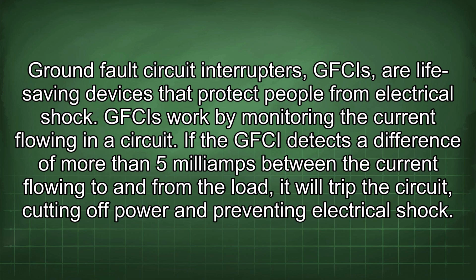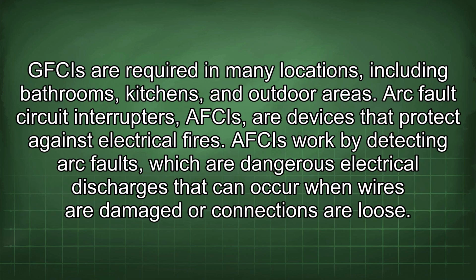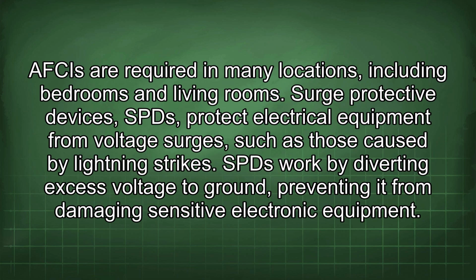Ground fault circuit interrupters, GFCIs, are life-saving devices that protect people from electrical shock. GFCIs work by monitoring the current flowing in a circuit. If the GFCI detects a difference of more than 5 mA between the current flowing to and from the load, it will trip the circuit, cutting off power and preventing electrical shock. GFCIs are required in many locations, including bathrooms, kitchens, and outdoor areas. Arc fault circuit interrupters, AFCIs, are devices that protect against electrical fires. AFCIs work by detecting arc faults, which are dangerous electrical discharges that can occur when wires are damaged or connections are loose. AFCIs are required in many locations, including bedrooms and living rooms.